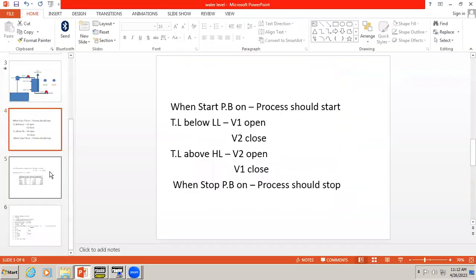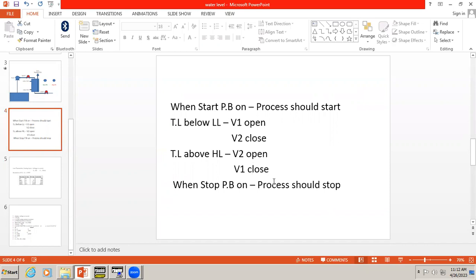The control condition is: when the tank level is below low level, valve 1 (inlet) should open so the tank level increases. Once it rises above low level, valve 1 should remain open. Only when it reaches the high level should valve 1 close and valve 2 (outlet) open — and vice versa.